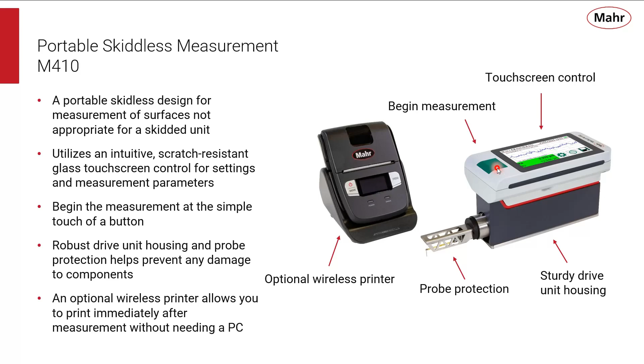It's got a robust drive unit housing and probe protection that helps to prevent any damage to components where the probe magnetically mounts, and can sometimes release before falling off and causing any major damage. This protection is even one more layer on top of that. We've got an optional wireless printer that allows you to immediately print your measurement without needing to connect to a PC or be near a PC.